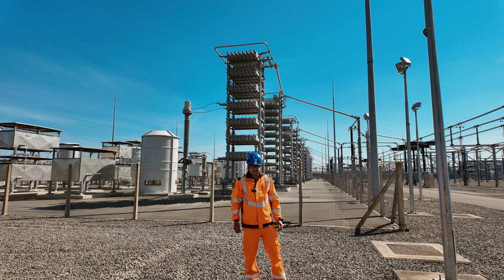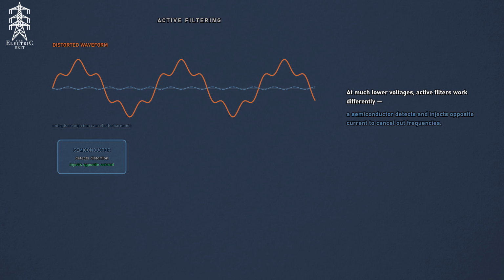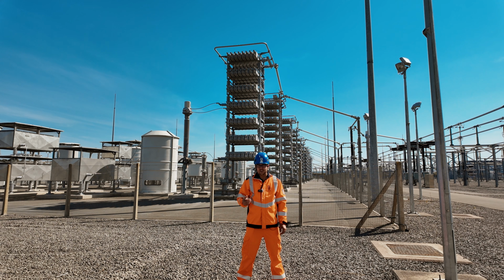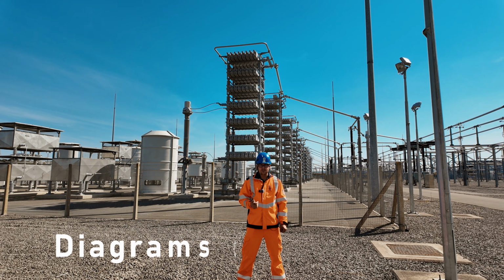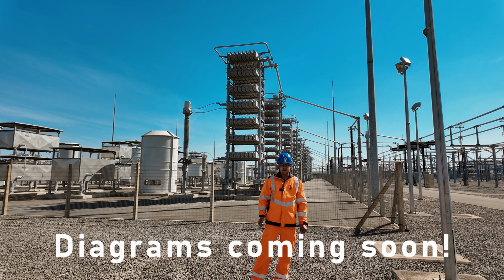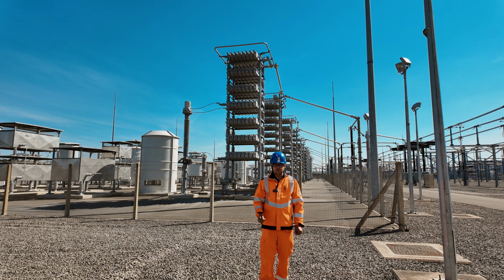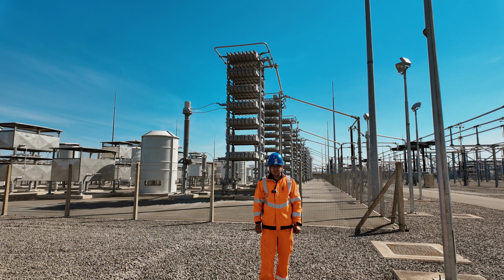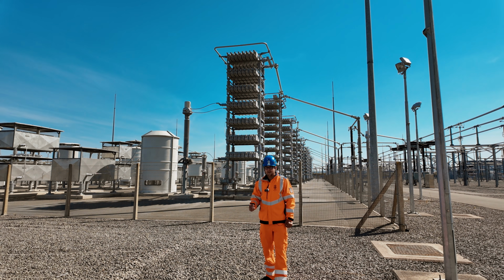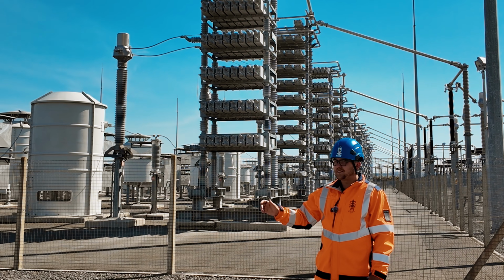But at lower voltages you can get active filters, which work a little bit differently, using a semiconductor to detect and inject opposite current to cancel out the frequencies. We don't do that on transmission voltages though, so the next best thing is tuning our filters to attack more than one frequency, where we can have single, double or triple tuned filters to attack 1, 2 or 3 frequencies. By adding extra capacitors and reactors to the filter, tuned to those other frequencies, we can attack more than one frequency with a single filter.